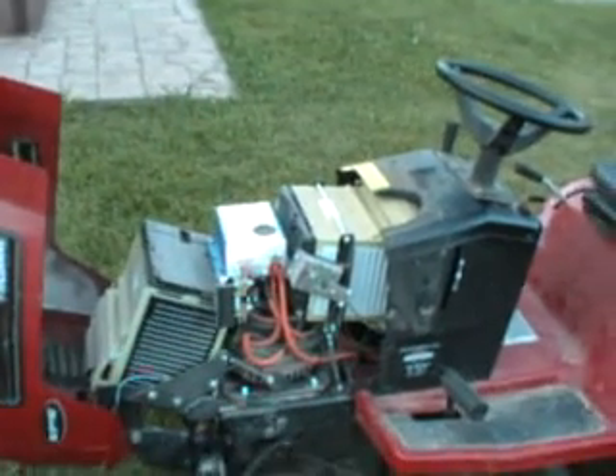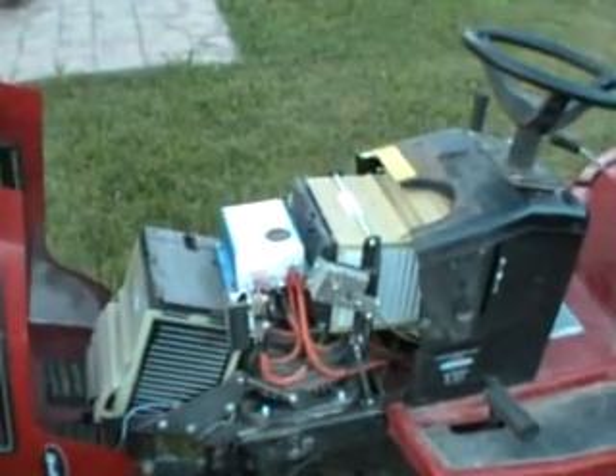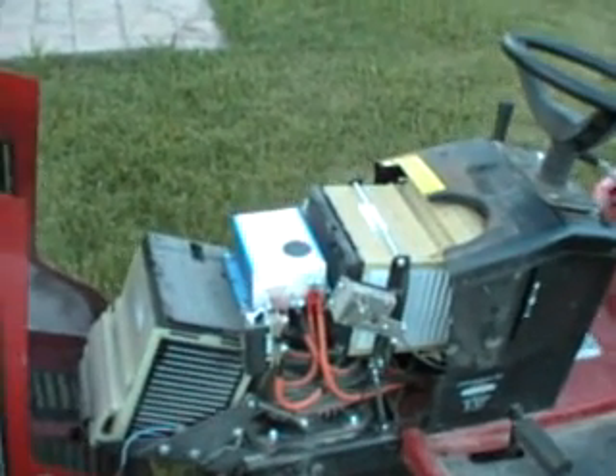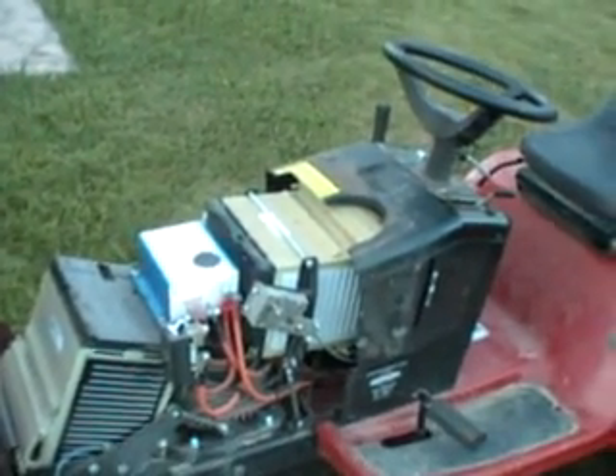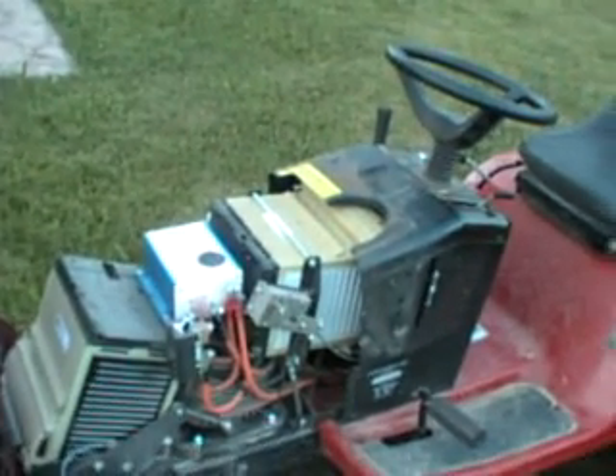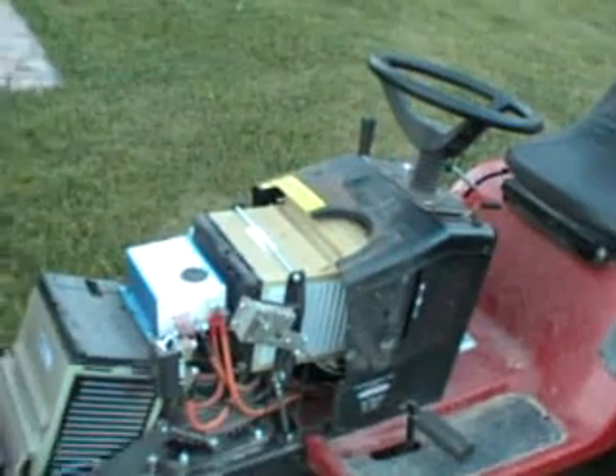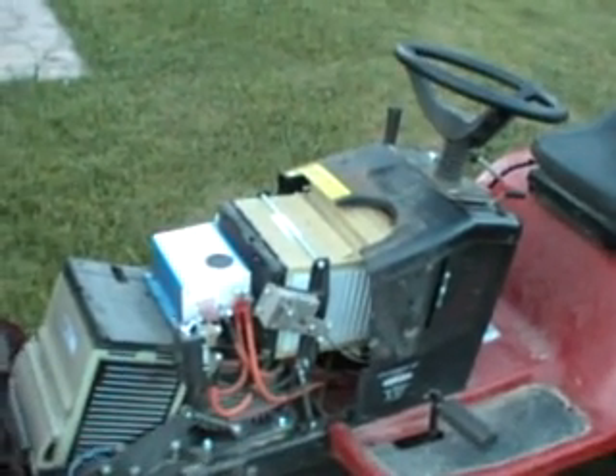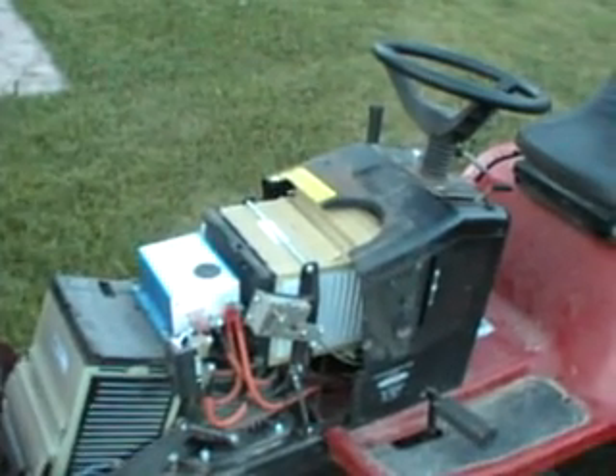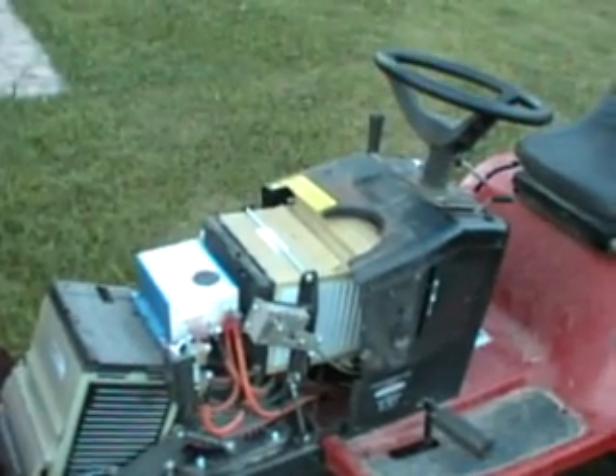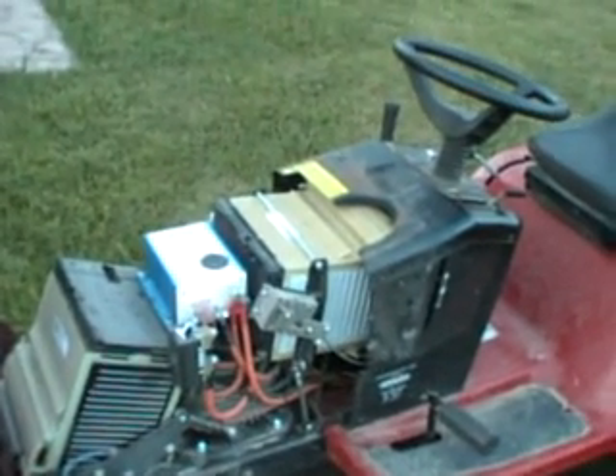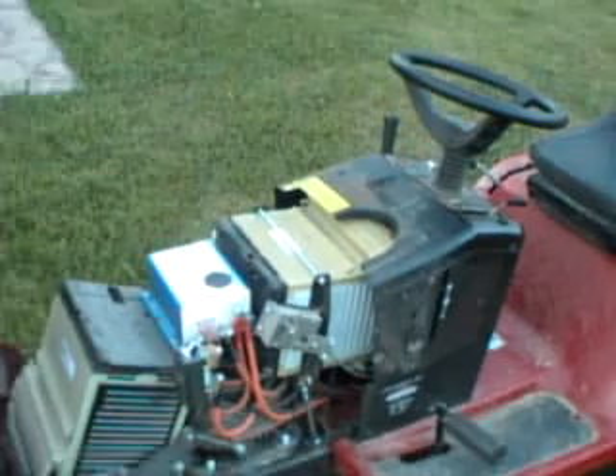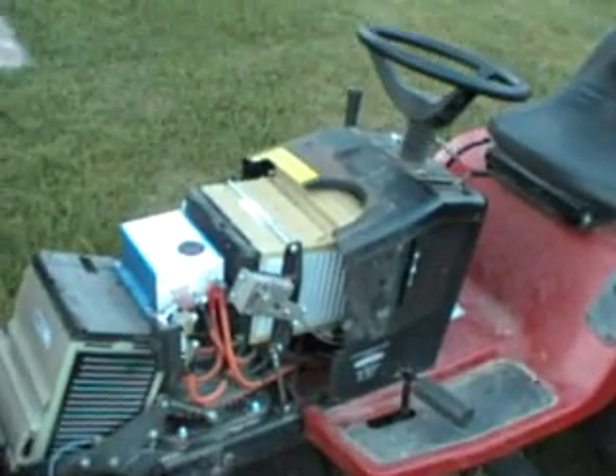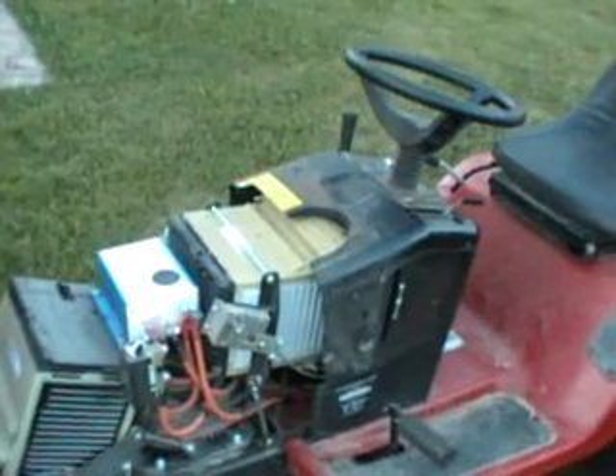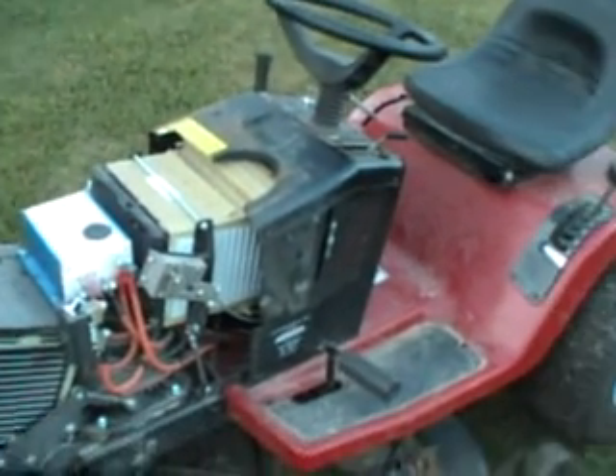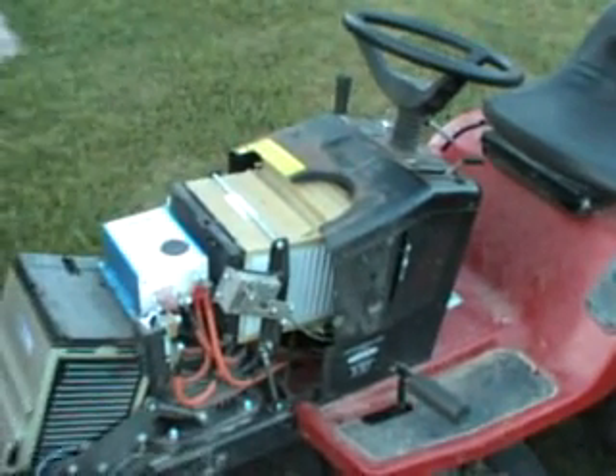The problem is, if you don't know about that, you go to charge the battery up again. I charge to 50 volts like I said, so you still have 50 volts going into this damaged battery, and those 4 volts that one cell would have taken now gets divided across the rest of them. If any particular cell is close to its storage capacity, you run into a situation where you can overcharge that cell, causing thermal runaway, and you can end up with minimum swollen cells, worst case a fire, and that's not good.